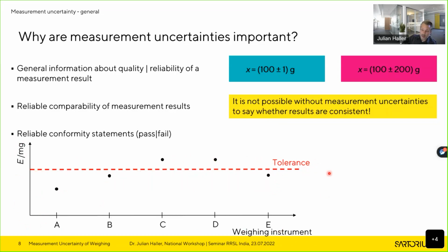And now what you would say now, of course, is that weighing instrument A, B, and E are in tolerance, and C and D are out of tolerance. But this looks different if you take into account the measurement uncertainties. Now you would honestly have to say, well, instrument A is in tolerance, that's a pass. Instrument D is out of tolerance, so it fails. But for the other ones, you just have to say, well, B and E, they are probably in tolerance, but it could be that they are also out of tolerance. So this is something like a probably pass. And for instrument C, you see it would also be possible that the true value is in tolerance. So for this instrument, you would have to state it is probably out of tolerance.